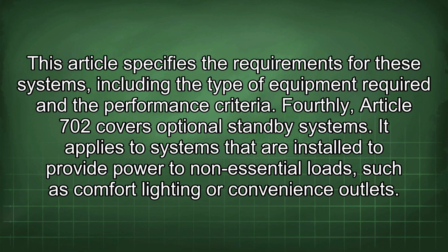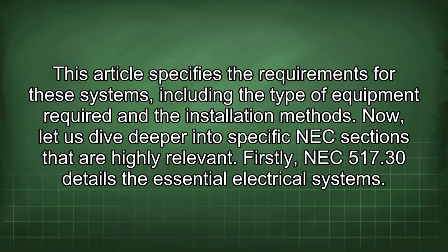Fourthly, Article 702 covers optional standby systems. It applies to systems that are installed to provide power to non-essential loads such as comfort lighting or convenience outlets. This article specifies the requirements for these systems, including the type of equipment required and the installation methods.